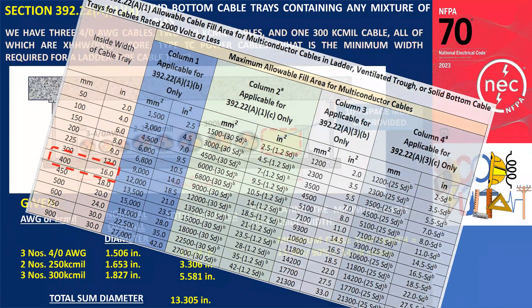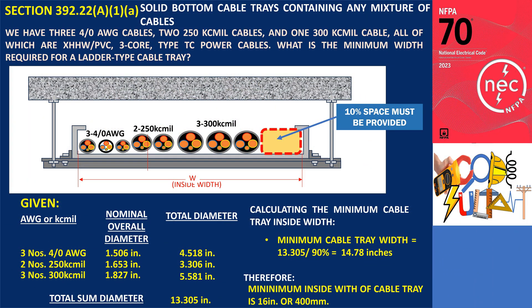Dividing this by 90% gives us 14.78 inches to determine the minimum width of the solid-bottom cable tray. Therefore, the minimum inside width of the solid-bottom cable tray should be 16 inches or 400 millimeters.